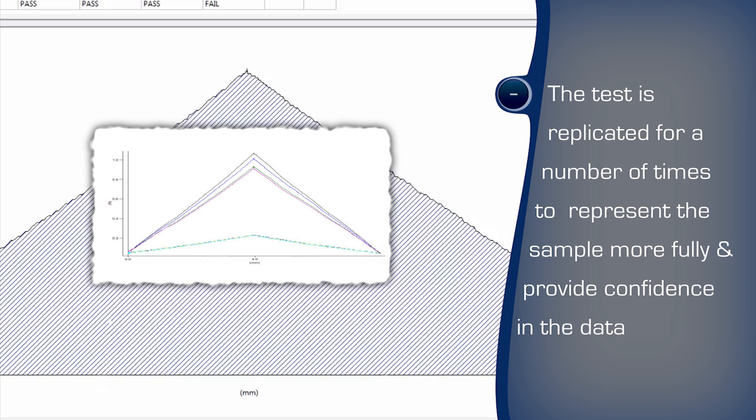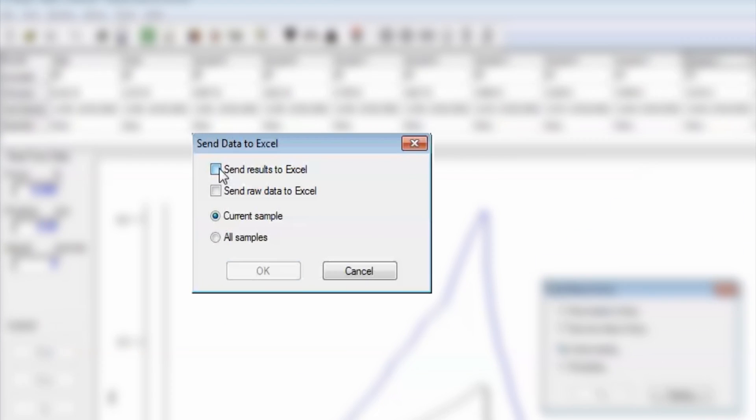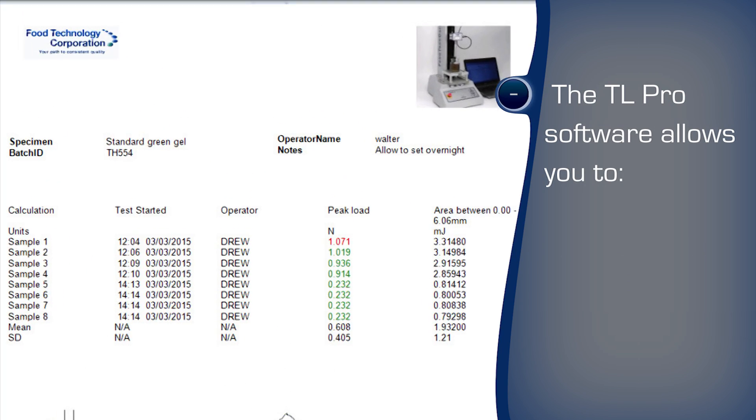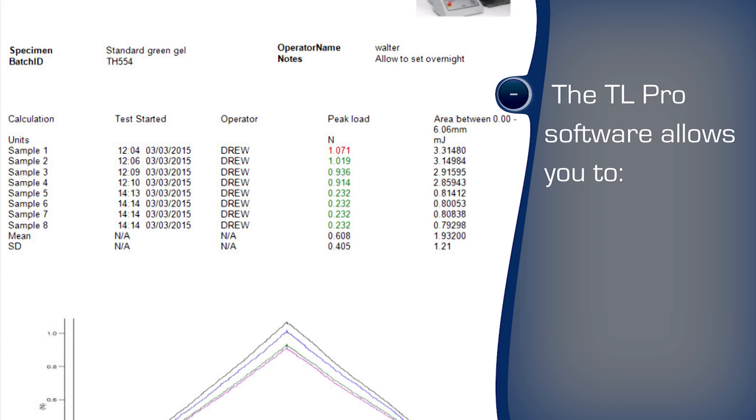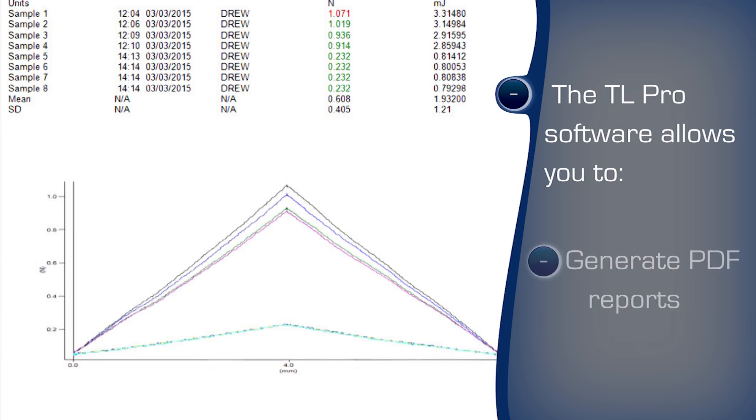The texture analyzer can repeat the test again and again. The TMS software can export to Excel for further examination and traceability, and format the results in a user-customizable style for clear reporting and an audit trail.